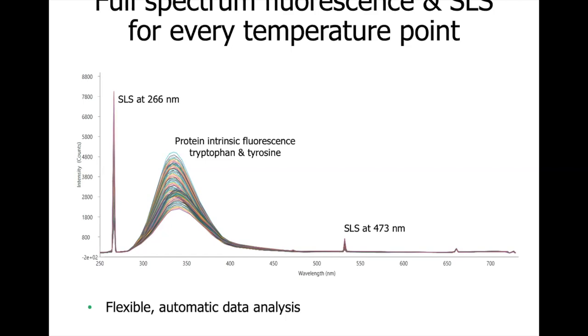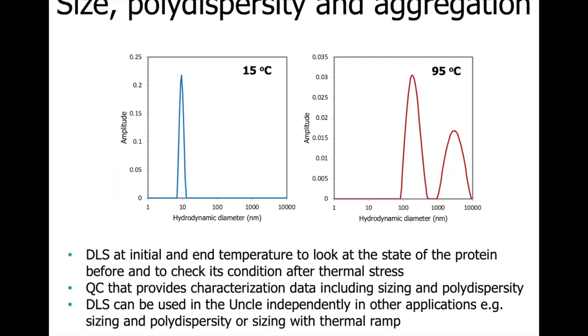The temperature profiles are built from the analysis of changes in SLS signals and full spectrum fluorescence as the temperature increases. As the samples are heated, the environment around aromatic groups undergoes disruption and consequently we observe changes in the fluorescence signal — both intensity and position of the emission band. The full spectrum fluorescence allows for flexible data analysis and in the UNCLE the data analysis is done automatically. The principle of SLS measurement is that larger particles scatter more light, and as proteins aggregate during the thermal ramp, the SLS signal increases allowing us to see when aggregation occurs.